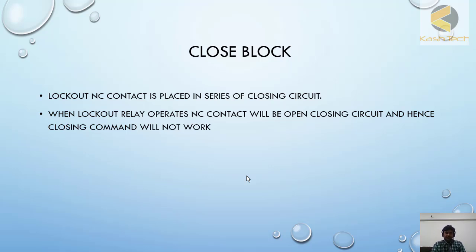Even if you are giving the closing command or some relay is giving closing command, the command can't be executed because DC supply is cut. So this is how lockout relay is used in a scheme.